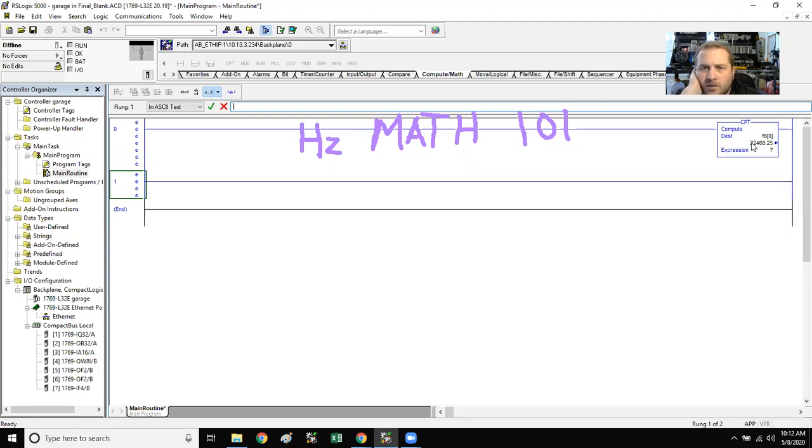All right. So right now, I need to figure out the high and the low of the fan speed. Yeah, if we were looking, it would be 0 to 60 hertz. So if it's 0 to 60 hertz, we need to convert that into a percentage.